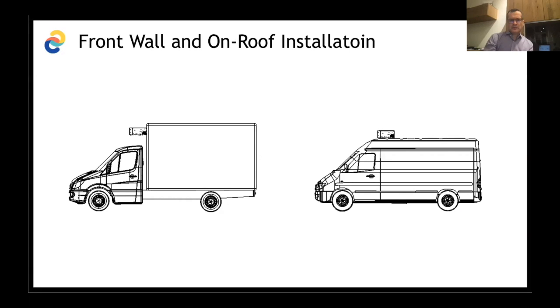What we were looking at in the design phase is that we can position for high refrigeration capacity. If you're going towards trucks, you can multiply the unit by putting two next to each other, and they don't harm themselves. By doing this, you have a redundant system for longer haulage, so you can provide cooling if one of the units is not in operation. The units, from their dimensions, can be installed next to each other for demanding higher refrigeration capacity, while still minimizing the risk bound to the use of R290.